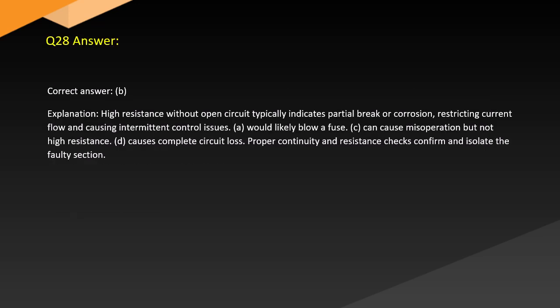Answer. Correct answer: B. Explanation. High resistance without open circuit typically indicates partial break or corrosion, restricting current flow and causing intermittent control issues. A. Would likely blow a fuse. C. Can cause misoperation but not high resistance. D. Causes complete circuit loss. Proper continuity and resistance checks confirm and isolate the faulty section.